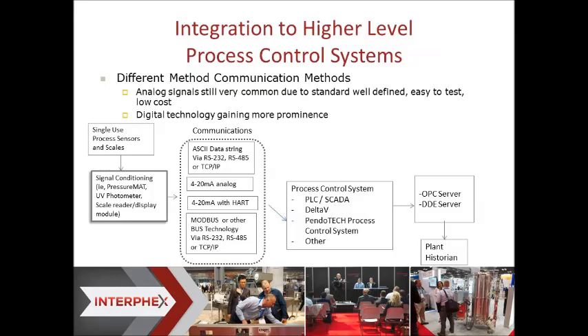So you have your sensor that's connected to a monitor, through some communication protocol, whether it's analog or digital. Some of the options are laid out here. That'll go to your process control system, such as a PLC or Emerson's DeltaV. And from there, they typically have the capability to be an OPC server and transfer data to the plant historian. So nothing has really changed here. It's just that the traditional sensor has been replaced by these two separate components in this diagram.